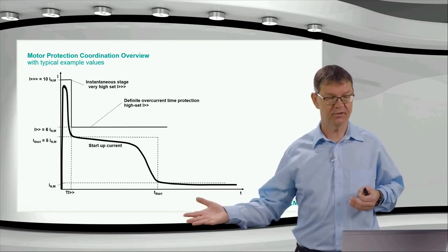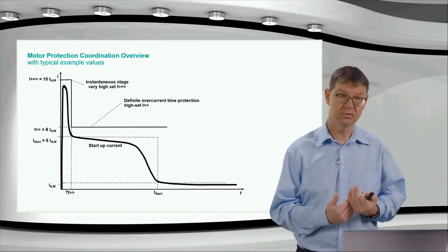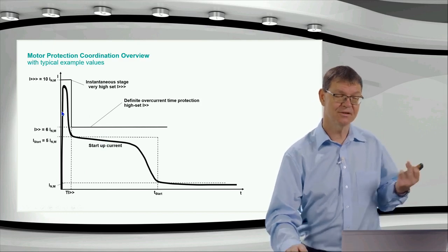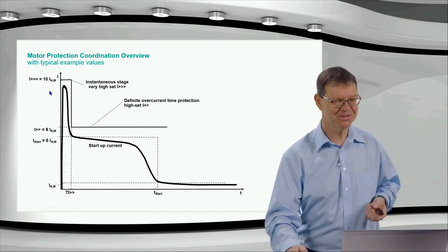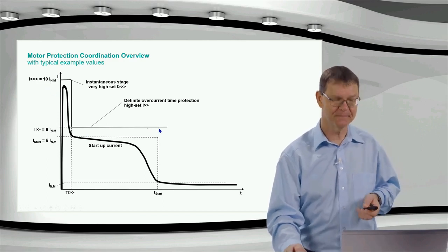Then during the startup phase, I can set a stage that is relatively close to the startup current with a certain margin. However, here I need to consider a certain time delay, of course, because otherwise this peak here endangers getting a wrong tripping.